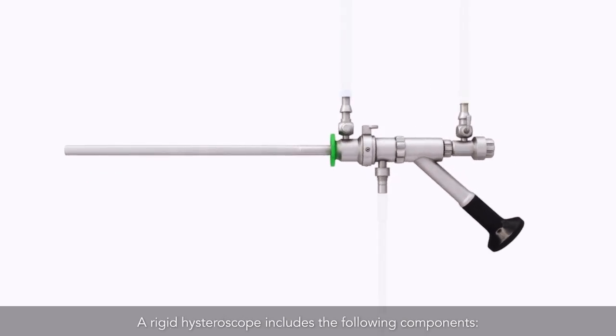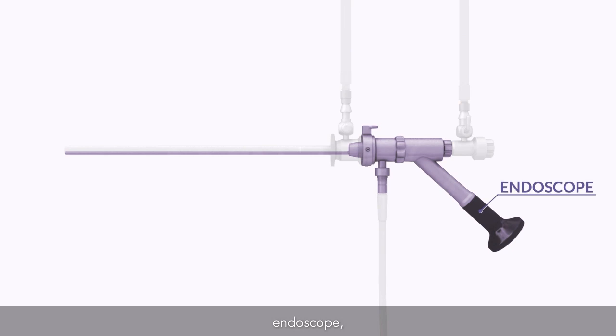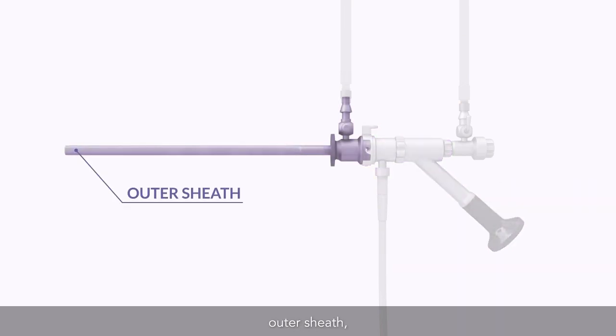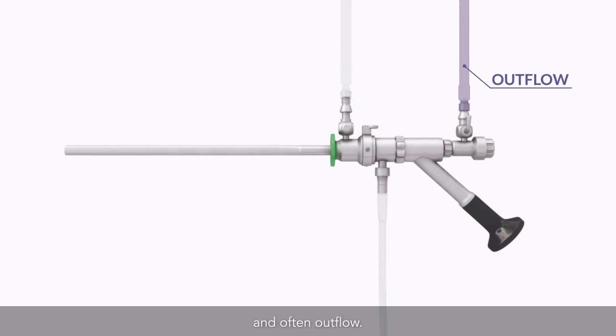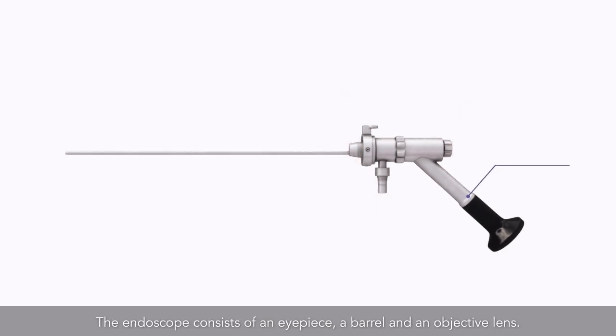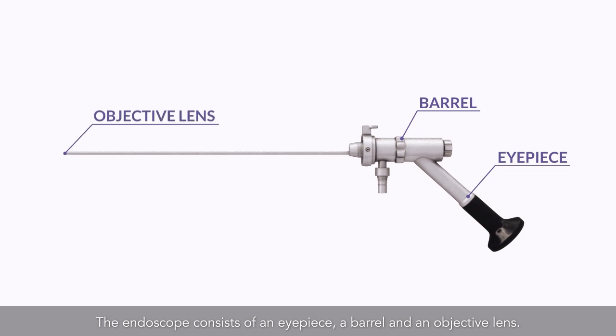A rigid hysteroscope includes the following components: endoscope, outer sheath, light source, inflow, and often outflow. The endoscope consists of an eyepiece, a barrel, and an objective lens.